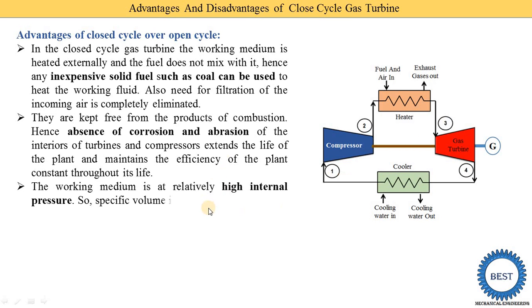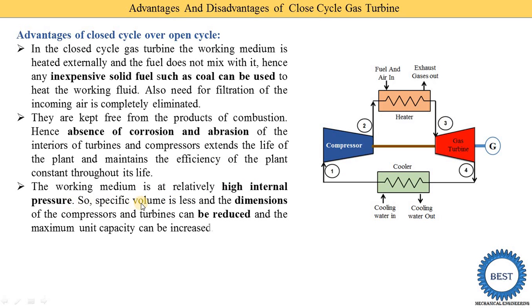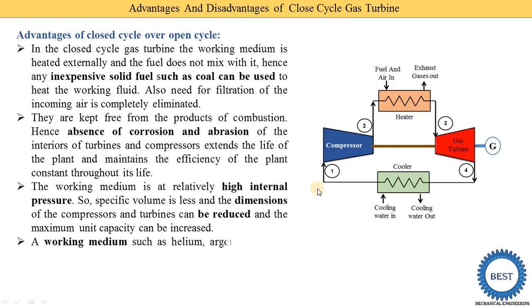The third advantage is that the working medium is at a relatively high internal pressure, so specific volume is less. At the inlet of the compressor, the pressure is above atmospheric, whereas in an open cycle the pressure is atmospheric. Because of this higher pressure, the specific volume is less, the dimensions of the compressors and turbines can be reduced, and the maximum unit capacity can be increased.